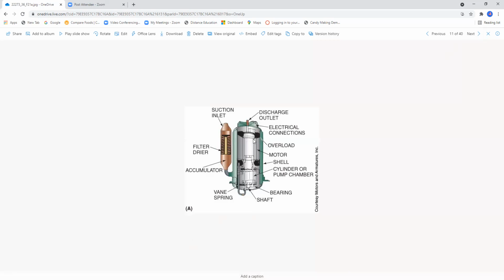Your overload, which is internal. Electrical connections are always at the top. Discharge in this case is at the top. Here you have what appears to be a filter dryer mounted on the side, and your suction pipe is brazed in right here.